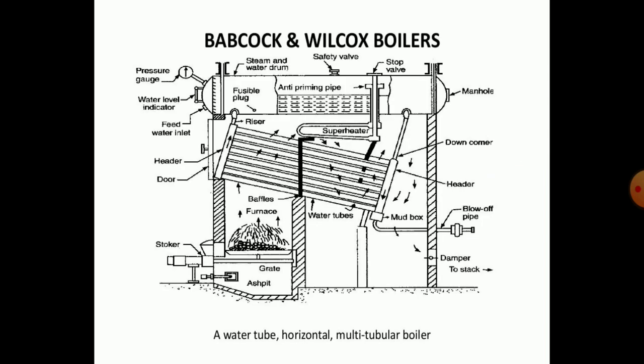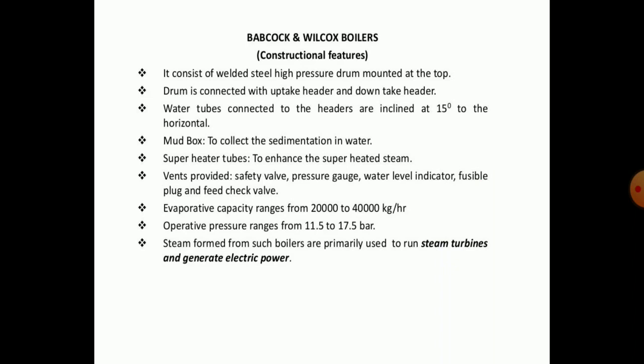Babcock and Wilcox boilers fall into the category of water tube boilers. In its construction, it consists of a welded steel high-pressure drum mounted at the top, connected with an uptake header and a downtake header. Water tubes connected to the headers are inclined at 15 degrees to horizontal, and a mud box collects sedimentation from the water. Superheater tubes are used to enhance superheated steam, while vents are provided for safety valves, pressure gauge, and water level indicator. Its evaporative capacity ranges from 20000 to 40000 kg per hour, while operating pressure ranges from 11.5 to 17.5 bar.